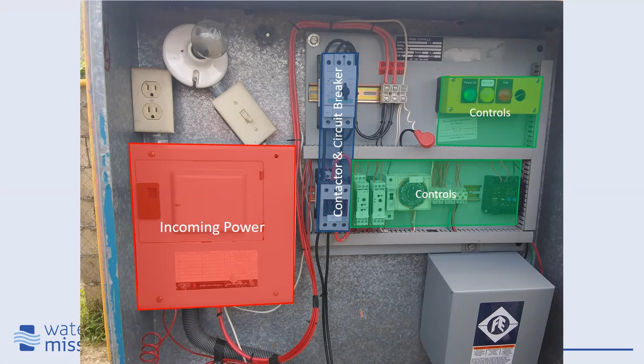When I look at this control circuit, I see some relays. There's probably some time delay relays. This looks like a timer, might be telling us the time of day. This looks like a voltage monitor. And this looks like status indication and also some operator buttons. Okay, so these are the three sides, the three components of the control panel.